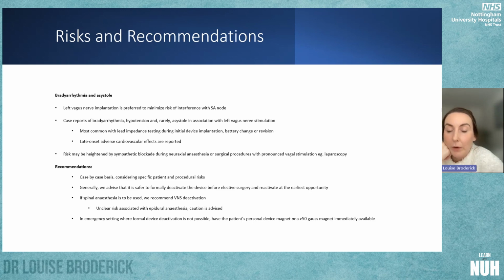In general, the working party agreed that it was safer to formally deactivate the device prior to elective surgery and to then have it reactivated at the earliest opportunity. We agreed that if spinal anaesthesia is to be used, we would again recommend that the device is deactivated unless there are other particular reasons to keep it activated. With regard to epidural anaesthesia, the risk is less clear because the sympathetic blockade may be less pronounced, but we do advise caution in this setting.